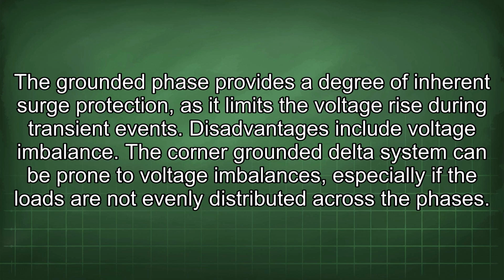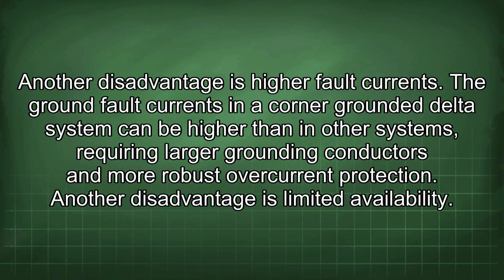Disadvantages include voltage imbalance. The corner-grounded delta system can be prone to voltage imbalances, especially if the loads are not evenly distributed across the phases. Another disadvantage is higher fault currents. The ground fault currents in a corner-grounded delta system can be higher than in other systems, requiring larger grounding conductors and more robust overcurrent protection.